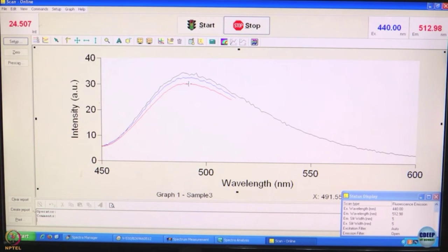There is always an optimal point beyond which there is no need to go, because if you see, the intensity is also going down with every successive measurement, which might indicate that your sample is going bad due to prolonged exposure to light. More often than not, that is what happens with organic samples especially. So, one needs to be careful and judicious and decide upon this integration time.